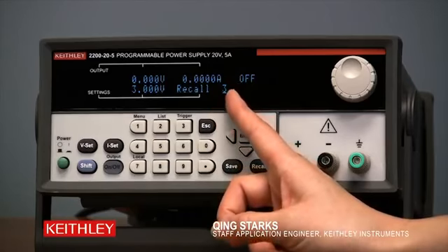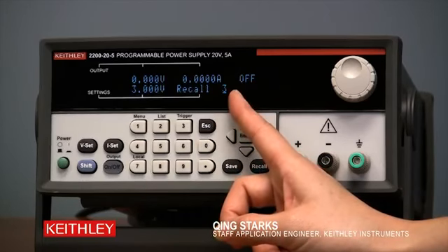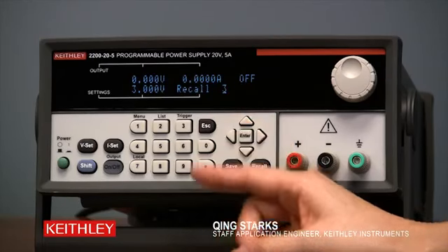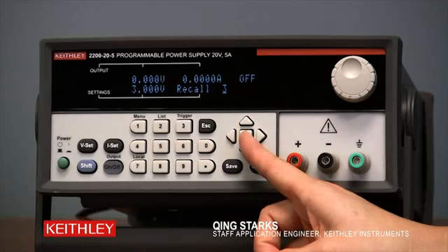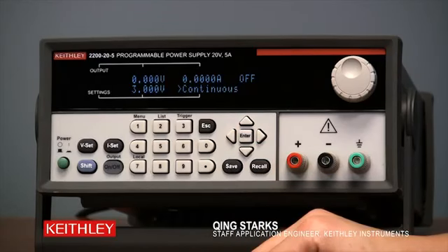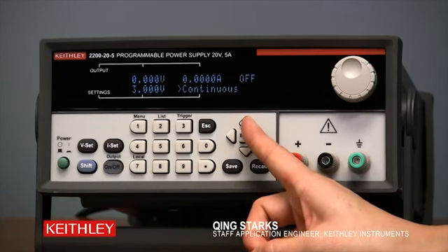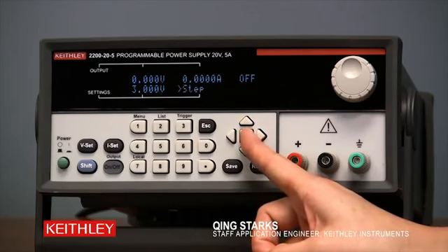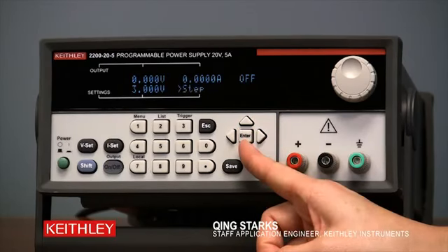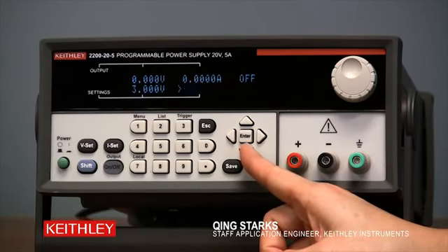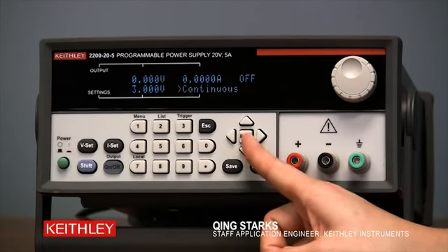The display will then show Recall 3, which means it's recalling from memory location 3. At this point, this is not important to us. Let's just press Enter. The next step, the power supply will prompt you to set continuous mode or step mode. Since this demo is using continuous mode, let's use the arrow button to move it to continuous and press Enter.